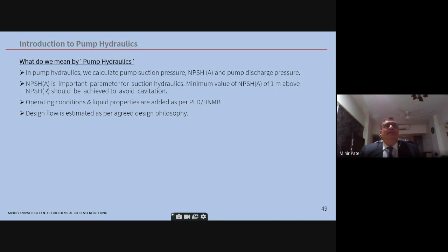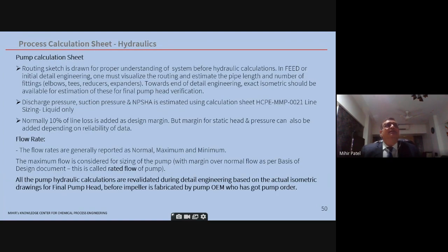NPSHA is important, again, as I mentioned earlier. Operating conditions and liquid properties are taken as per the process flow diagram and heat and material balance. Design flow is estimated as per the agreed design philosophy. So design flow, basically what I mean is how much excess to keep, what design margin to keep. This is decided in the basis of design, which a process engineer makes at the start of the project. Then the process calculation sheet for hydraulics. So again, these are the steps one has to follow.